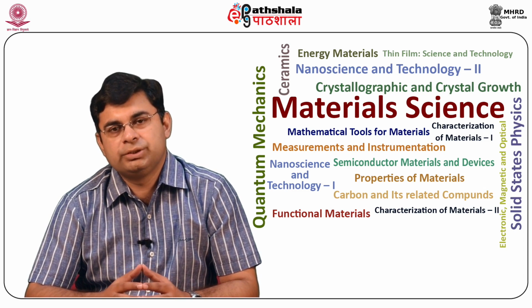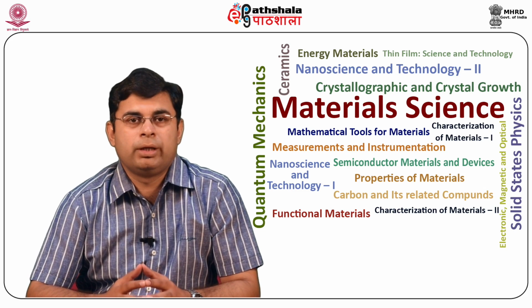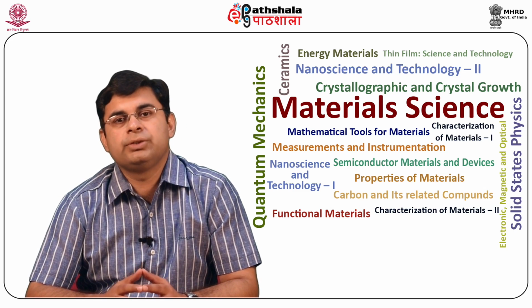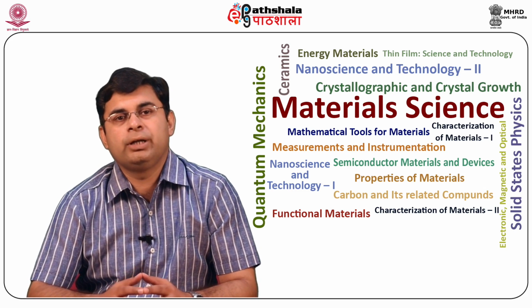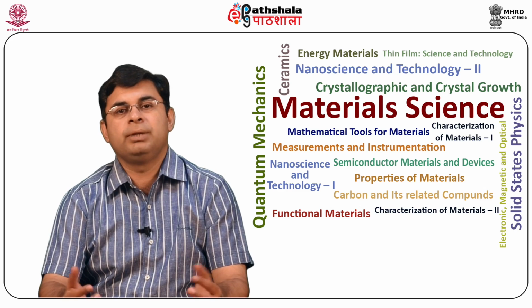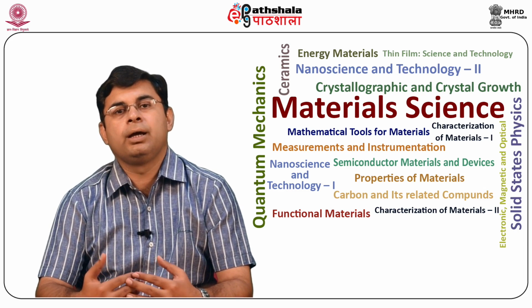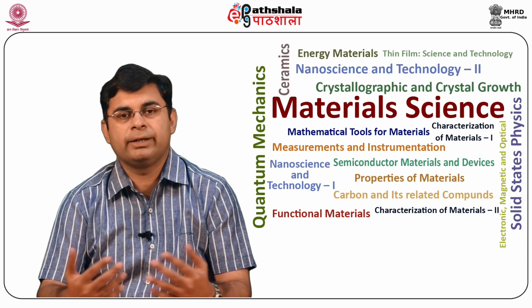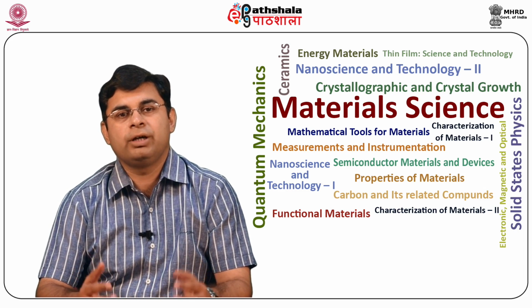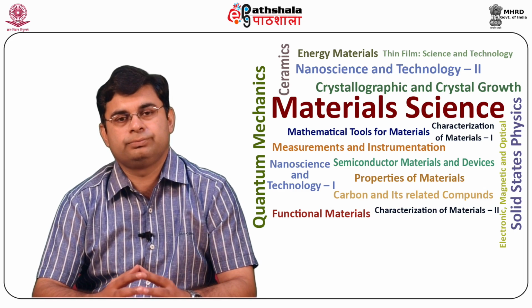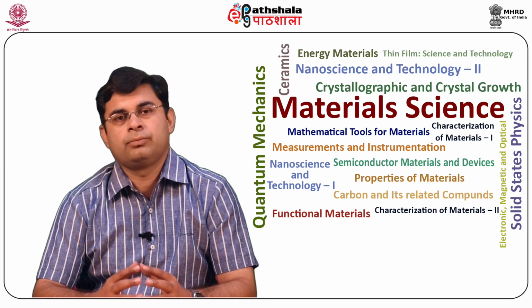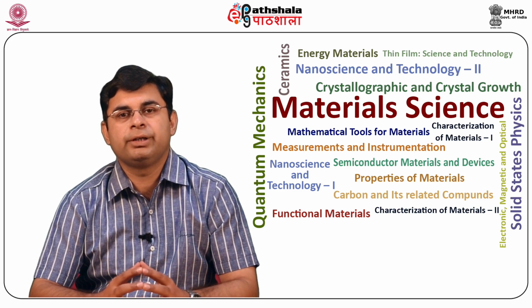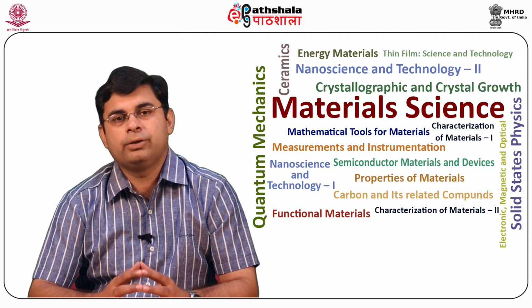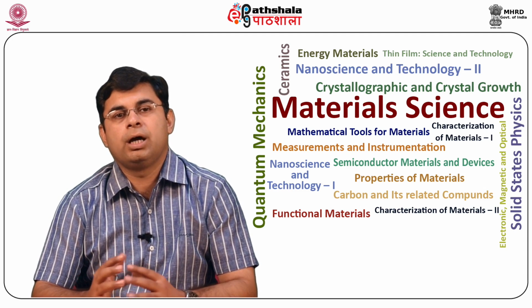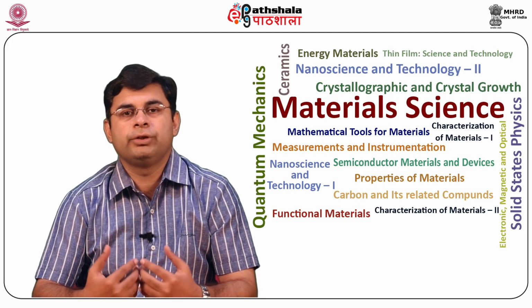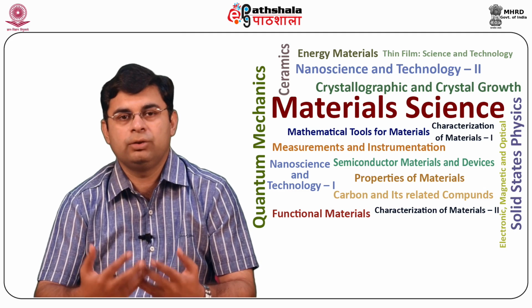For routine measurement of bridges, pointer instruments are used. It is more advantageous if such instruments are made phase selective. Predominantly, pointer instruments are moving coil milliammeters operated via some arrangement of copper oxide rectifiers and have a working range of 40 Hz to 1 kHz. Modern bridges are regularly fitted with an amplifier. A heterodyne or a beat tone detector is used for high audio or radio frequencies, or frequencies above 3 kHz.